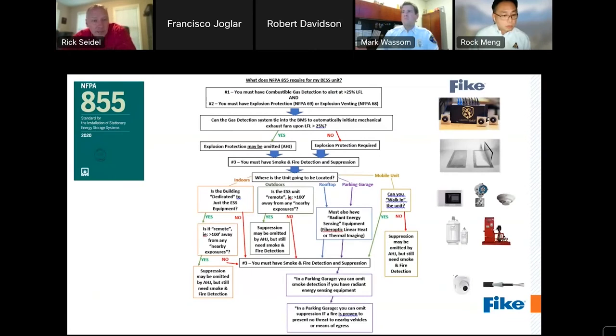This eye chart is my best interpretation I can make out of the questions and answers that NFPA 855 lays out to offer you guidance as to what to do when you have an energy storage system from a protection standpoint. You can see at the very top, number one requirement, regardless, before any questions are asked, is you must have combustible gas detection to be able to provide an alert, and that is what the off-gas detection system can provide.